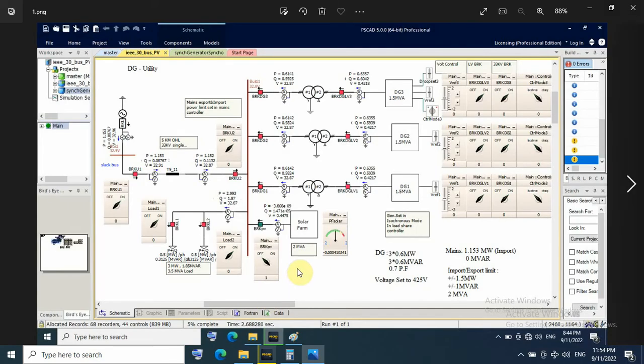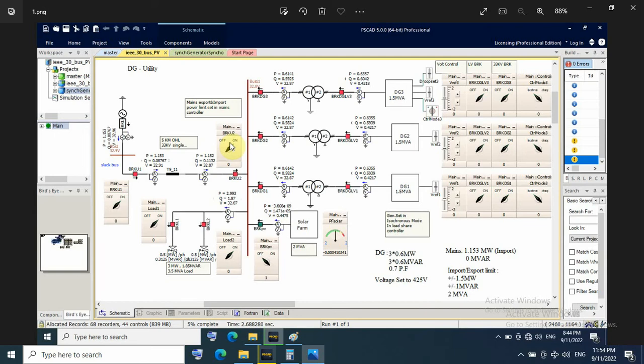So let us start with DG only. I have DG and utility, no PV. So for this case I have three gensets. Each genset generates 0.6 megawatt and 0.6 megavar at 0.7 power factor. The voltage setting about 425 volts.